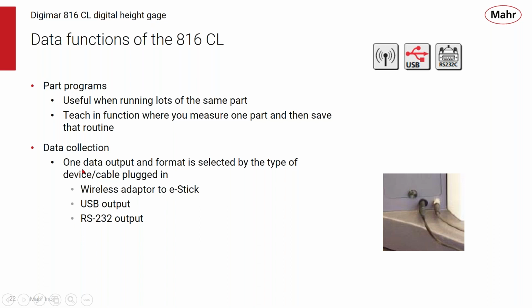With the data output function, you can collect data wirelessly through our add-on modules, use the USB port, or use RS-232. The unique thing about all the Mahr products is that there's one output, and the cable you choose selects which format you want. From that one connector on the back of the product, you can use a wireless adapter to our eStick, a cable for USB output, or the RS-232 cable to get that output format.